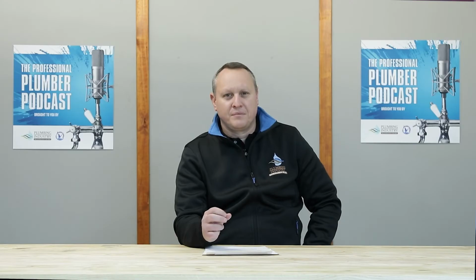So in short, Willem, there are two things one must remember for a shutoff valve. Number one, there must be one before the PRV, a pressure relief valve, or a pressure control valve. Let's call it a PCV. We just usually call it a PRV from habit, but it's actually a PCV. So there's got to be one upstream there. And number two, it's got to be in a position which will allow easy maintenance of all the components on a geyser. So those are the two things to remember.